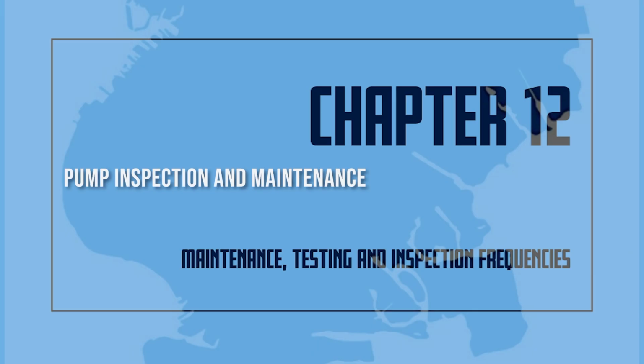When the pump is in operation, a small water leak on the pump bearings is desirable and should not be considered a malfunction. If an automatic controller operates the fire pump, the pump shall be activated by reducing the water pressure in the system. This can be done by opening the test drain or initiating a large water flow from the system. By starting the fire pump this way, the certificate of fitness holder can determine if the automatic controller is working properly. Care should be taken to make sure that the pump does not overheat while conducting the test.